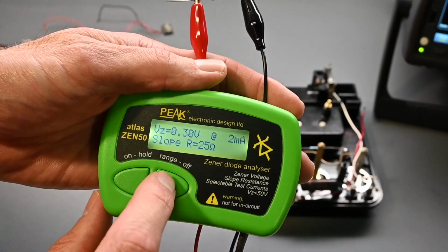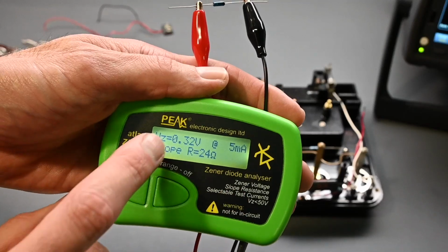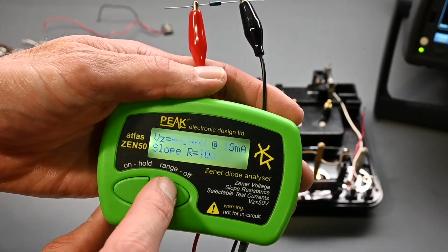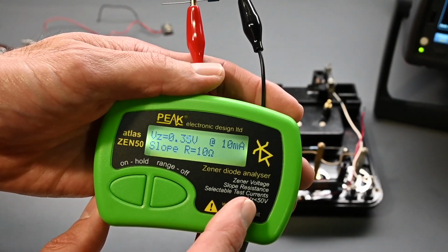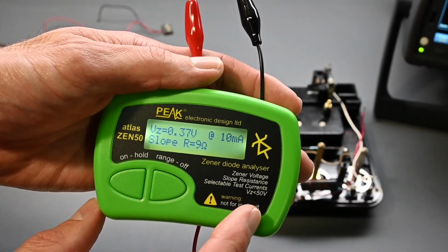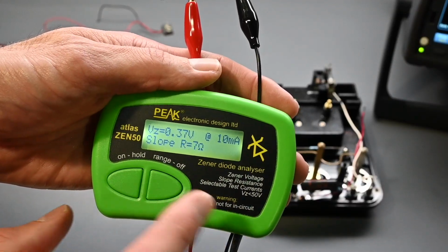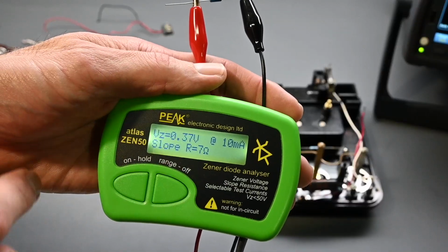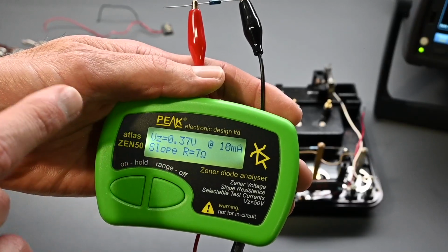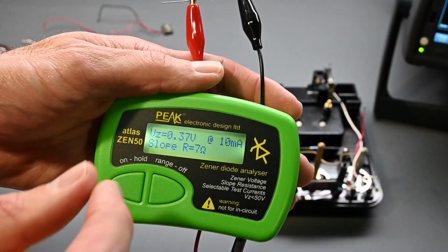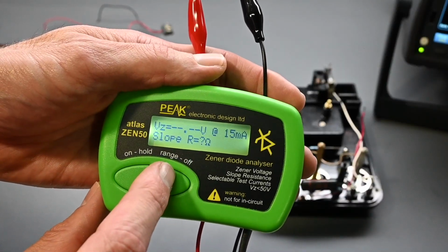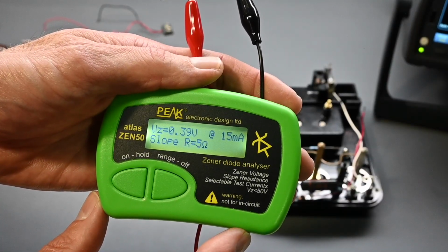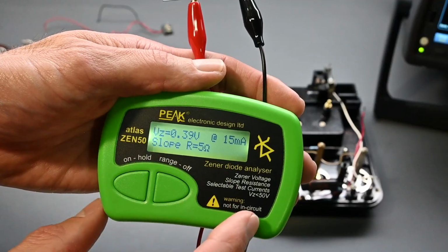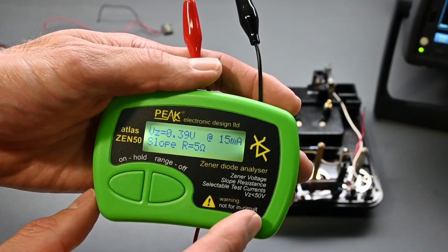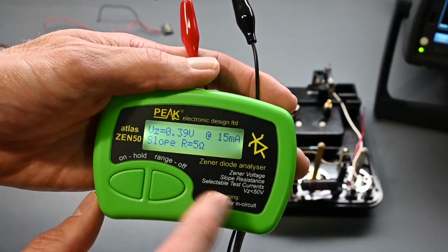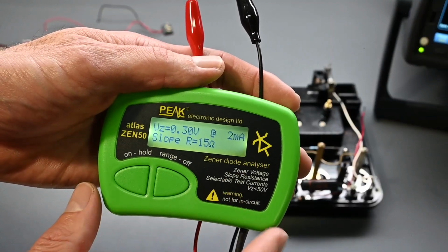Okay, so going back here, if we go to 5 milliamps, you can see the values change a little bit. 10 milliamps of current, values change again. Have to settle in just a little bit. This is actually taking an update about every 2 seconds. So if things change just a little bit, it will update. It's not just a one-time measurement. And 15 milliamps. So you can see the slope resistance value changes quite a bit. Forward voltage drop changes as well. Go back to 2 milliamps, it just cycles around again.